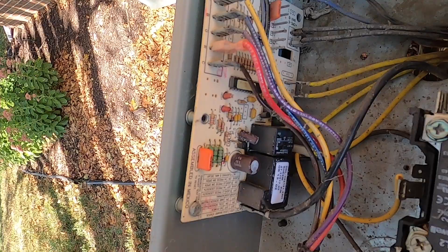And you can see here, in this case, the purple wire is connected to my white wire and is sending that voltage back. You can see that's on the D for defrost. It's trying to kick on the defrost cycle in cool mode, which it does not need to do. So we're going to pull this out of there. There's a couple of screws here. We're going to carefully swap it for the new one, which I ordered and have on hand, and we'll go from there.